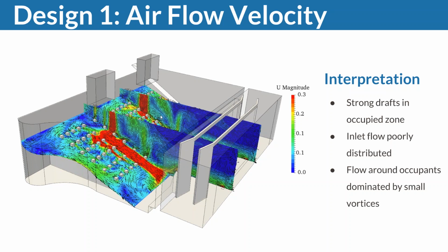It's poorly distributed, right? So I said that already earlier. So one troubleshooting could certainly be a diffuser. And then we've got all sorts of things happening here, right? Here there are some flows at the side that we don't really like, where the velocity goes up. So overall, that doesn't seem to be too smart, right?